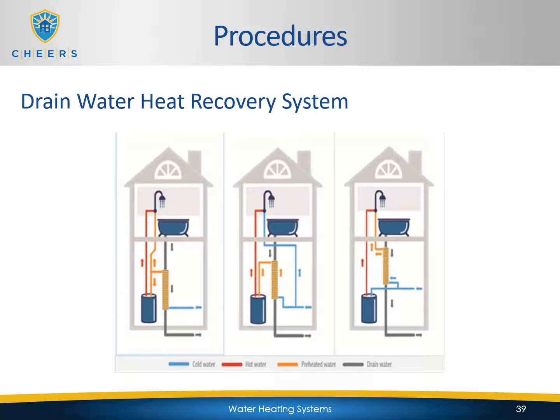Now the one in the middle there, same concept. You have your gray line, which is your drain going out, passing through the heat exchanger. And now in this one, we have two cold water lines. The cold water line will split off, and one of the runs will go through the heat exchanger, get preheated, and go into the water heater, which does help because now the water heater doesn't have to work quite as hard to heat up the water, but it's going to be sending cold water up to that shower. So we're still going to need just as much hot water to get the same temperature as if we had no DWHR system installed. So it makes the water heater a little more efficient, but you're still needing to use just as much hot water to get that same temperature.